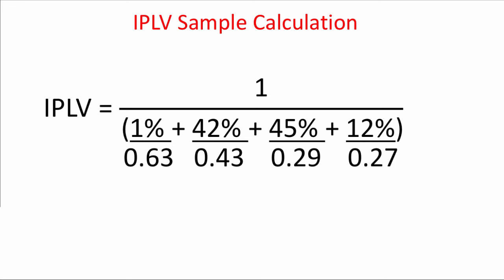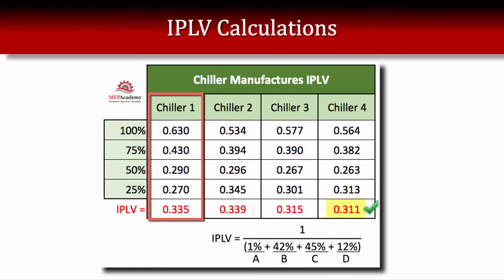Here are the values: at 1% of the time the EER is 0.63; 42% of the time it's 0.43; 45% of the time it's 0.29; and 12% of the time it's 0.27. You can see the chiller is hardly running at full load, and full load actually has the worst EER. Using a spreadsheet with those four values — 0.63, 0.43, 0.29, 0.27 — the result is an IPLV of 0.335.